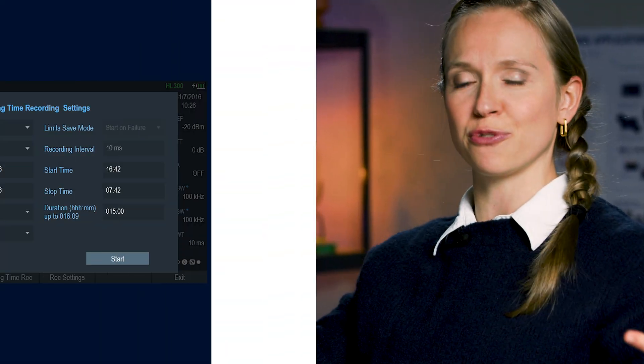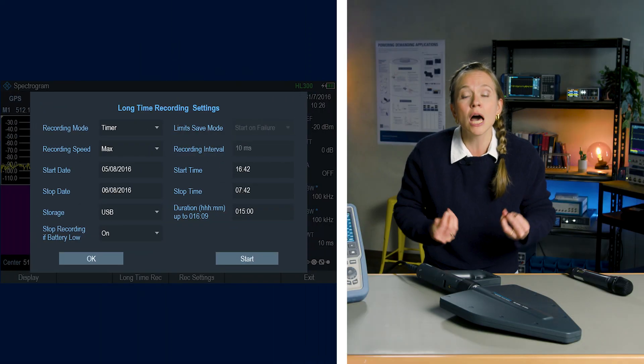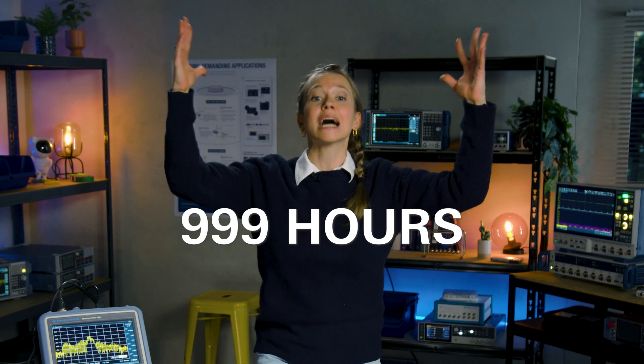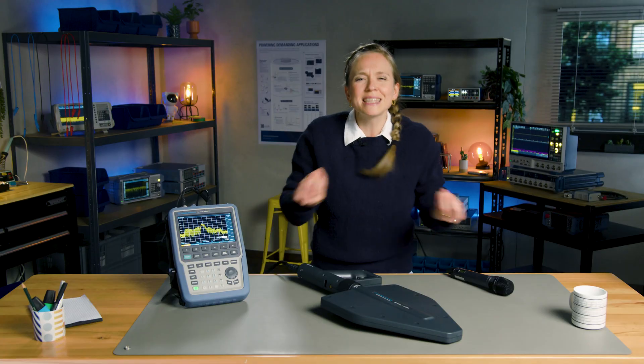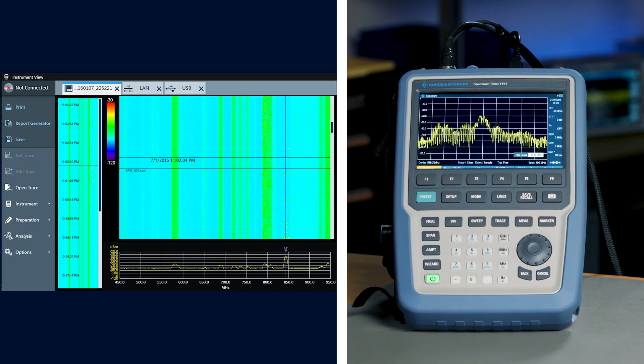To capture intermittent interference, the FPH has a standout feature, Spectrogram Recording, which allows you to capture and analyze up to 999 hours of signal data. You can then use Instrument View software for detailed analysis and documentation.